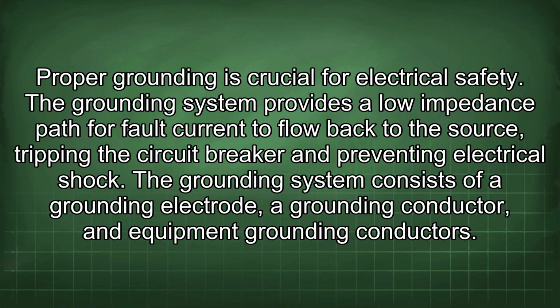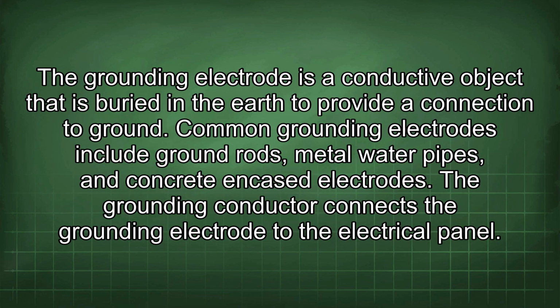Proper grounding is crucial for electrical safety. The grounding system provides a low impedance path for fault current to flow back to the source, tripping the circuit breaker and preventing electrical shock. The grounding system consists of a grounding electrode, a grounding conductor, and equipment grounding conductors. The grounding electrode is a conductive object that is buried in the earth to provide a connection to ground. Common grounding electrodes include ground rods, metal water pipes, and concrete encased electrodes.